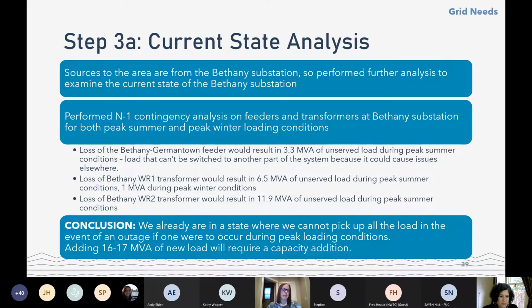We also found that our Bethany transformers did not have full redundancy during peak summer, and one of them did not have it during peak winter either. So we already had system issues with redundancy, and we didn't want to add 16 to 17 MVA of new load to that existing system because that would make things worse.